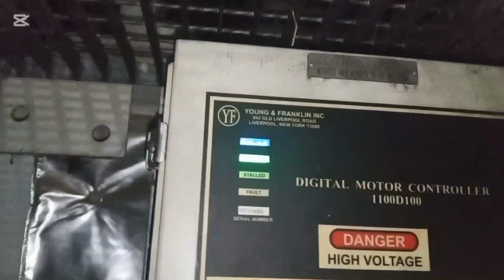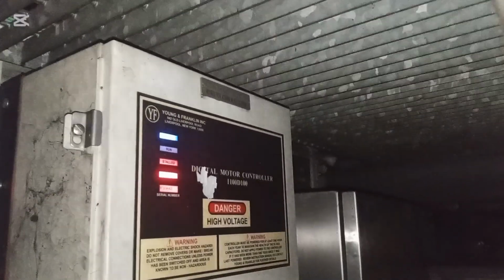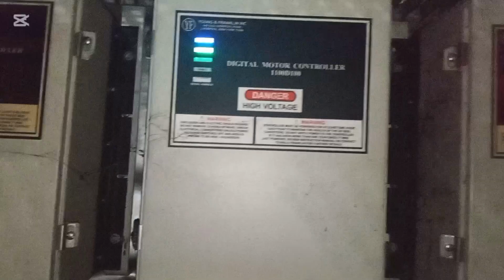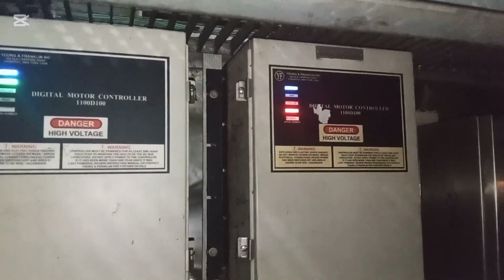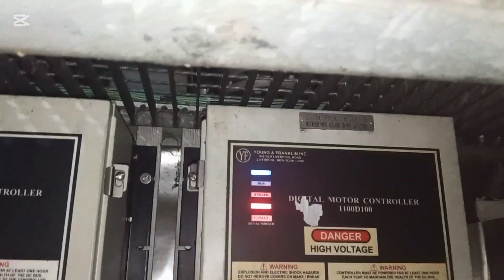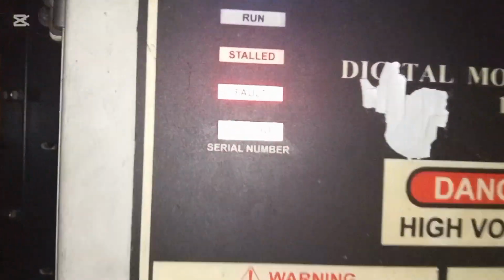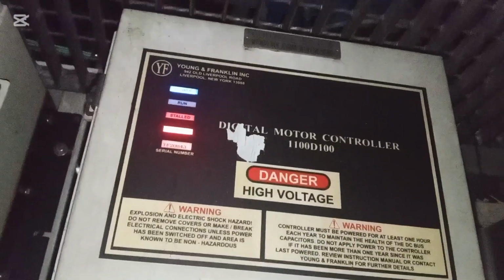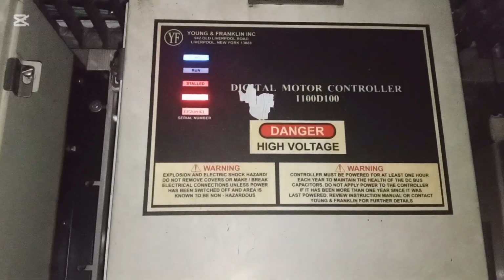For this gas turbine there are three valves, and for these three valves there are three individual motor controllers. Two of the controllers are okay and one is showing only a single alarm, and from this alarm we came to the decision that the controller is not functioning properly. In our store there is a new controller, and we tried to interchange the new controller with this one to start the gas turbine instantly.